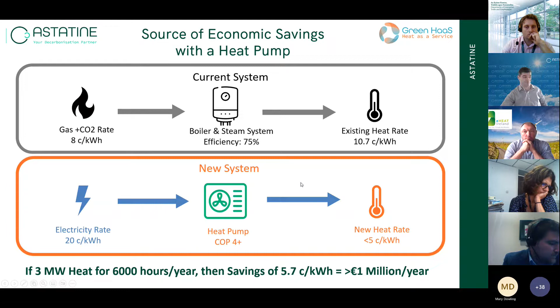That $1 million a year saving has to justify the upfront costs, which go not just to paying for the heat pump, but also the integration costs of putting it in. This is a very typical scenario we see on site: a 3 megawatt heat load, 6,000 hours, a COP of 4, so they can save $1 million a year. Taking advantage of the various supports mentioned by both Fergus and Aileen, we can usually pitch around a 3-year payback for good sites meeting those criteria.